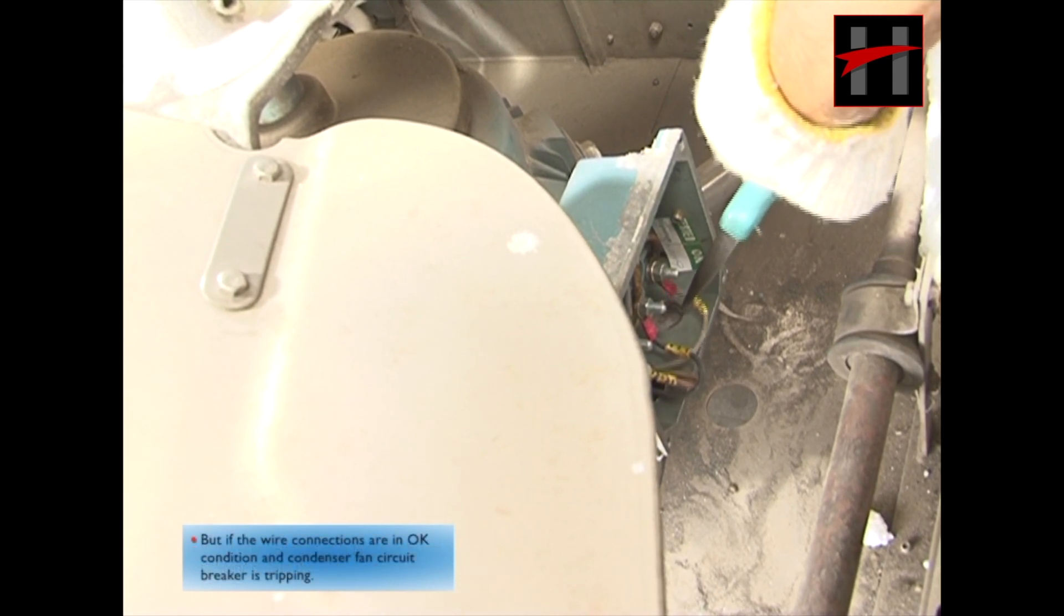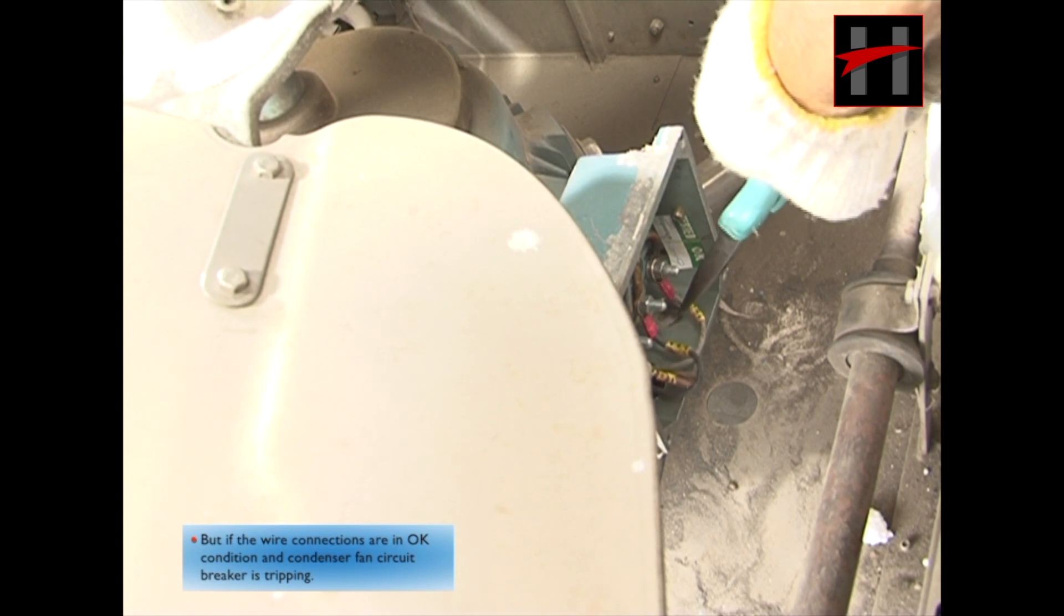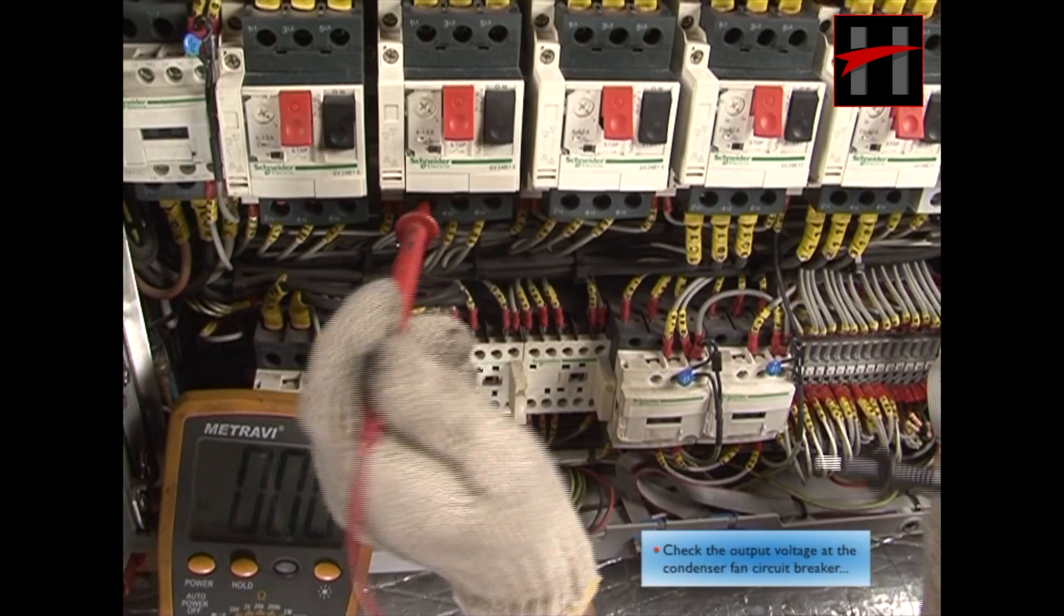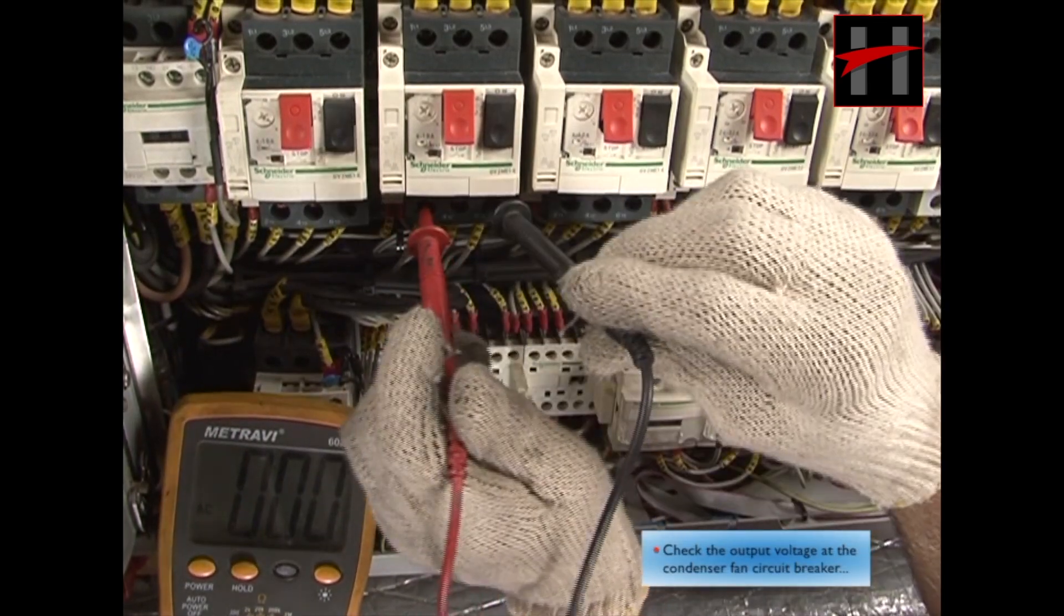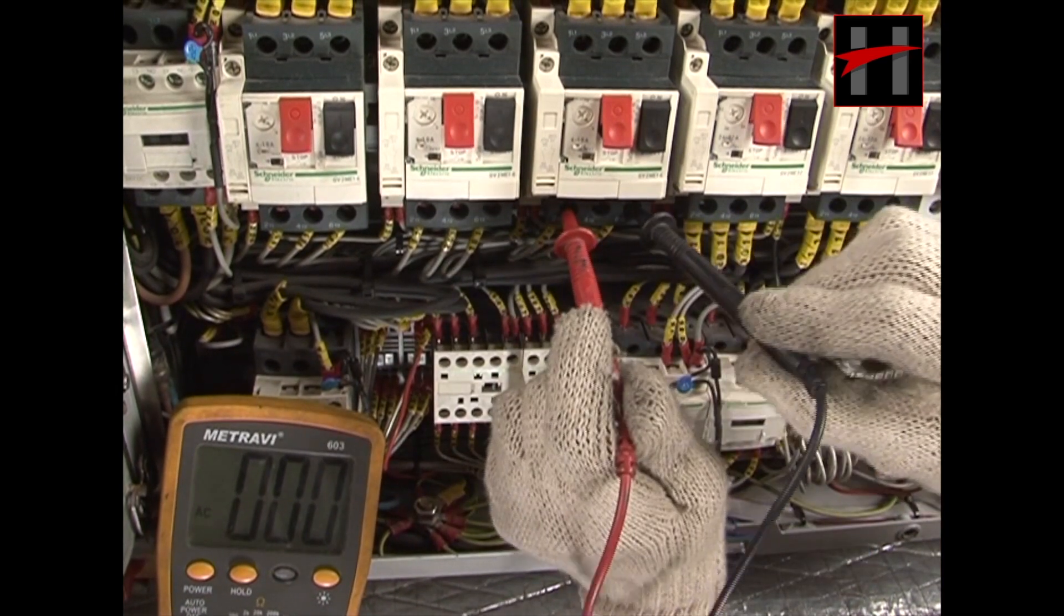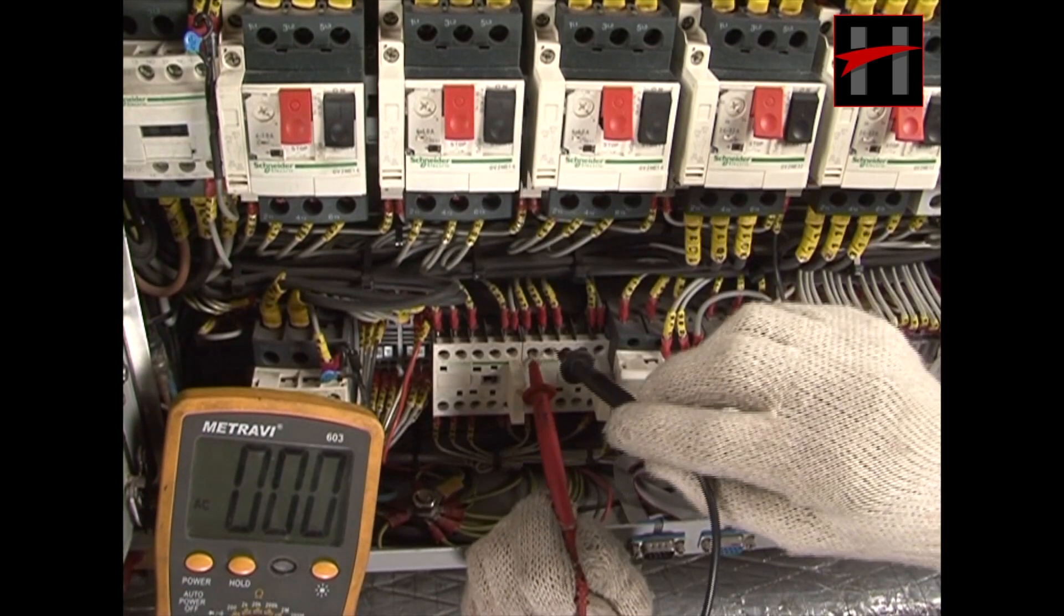But if the wire connections are in okay condition and the condenser fan circuit breaker is tripping, check the output voltage at the condenser fan circuit breaker and the circuit breaker contactor.